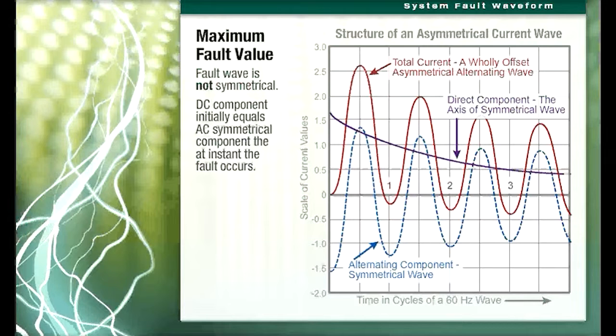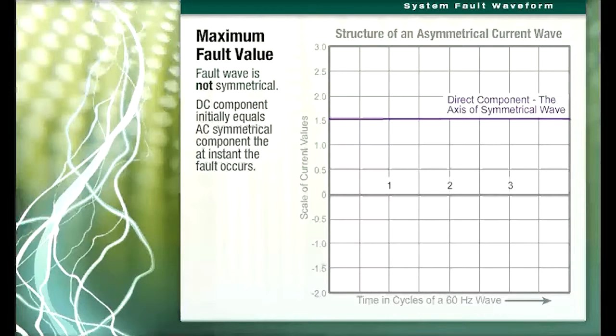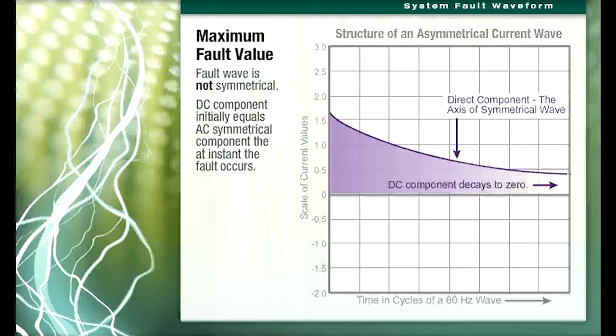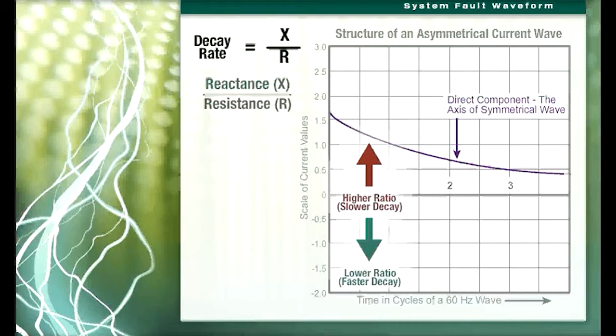In a theoretical system with zero resistance, the DC component of fault current would remain a constant value. However, in an actual system where resistance is present, the DC component decays to zero as the stored energy it represents is expended in the form of I²R heat loss in the resistance of the system. The rate of decay of the DC component is exponential and is a function of the reactance-to-resistance ratio, X over R, of the system from source to fault. The lower the X over R ratio, the more rapid is the decay of the DC component.